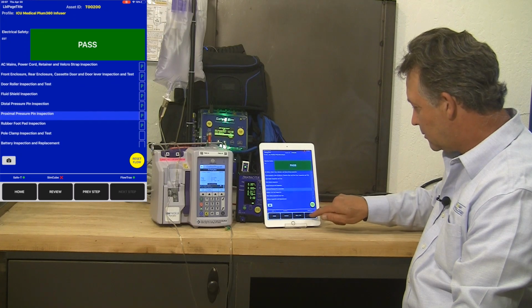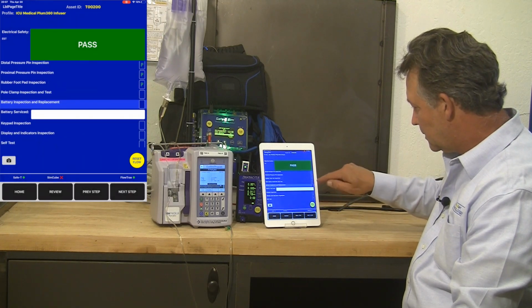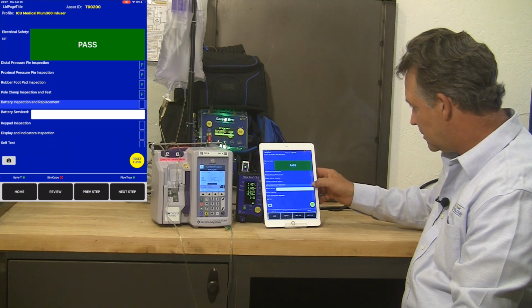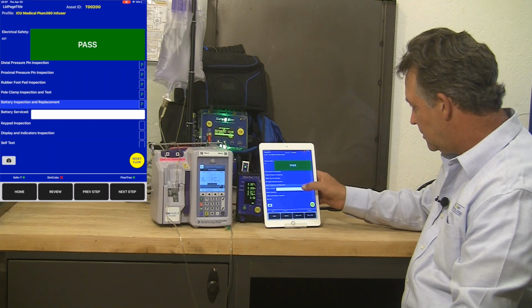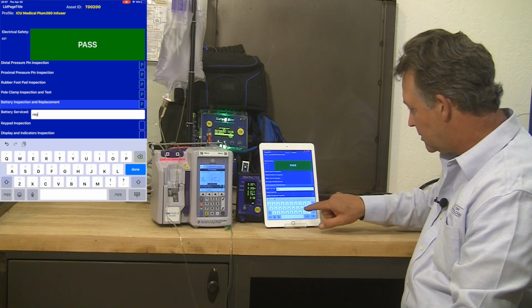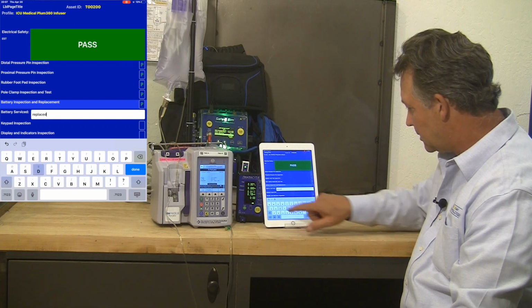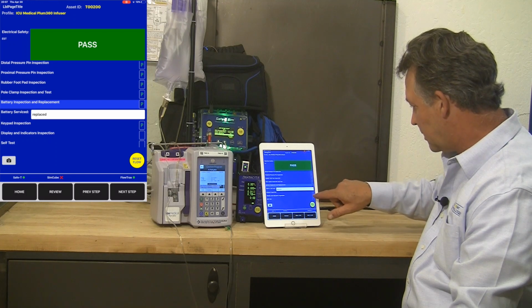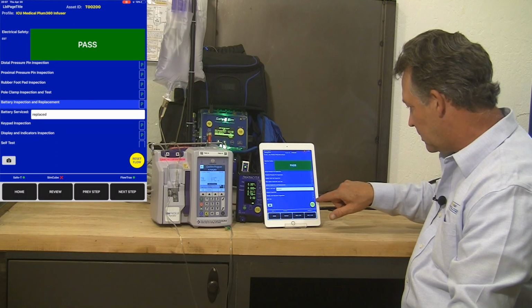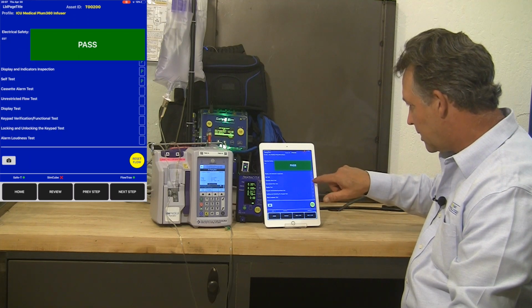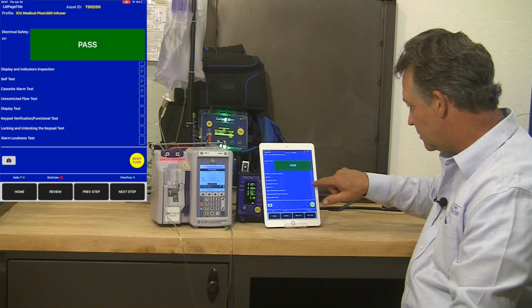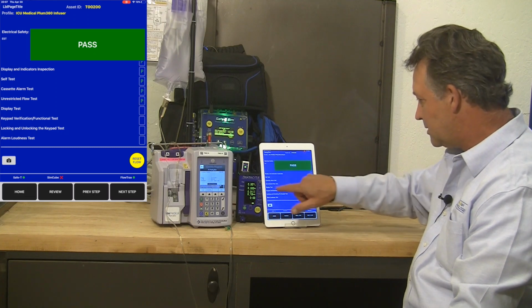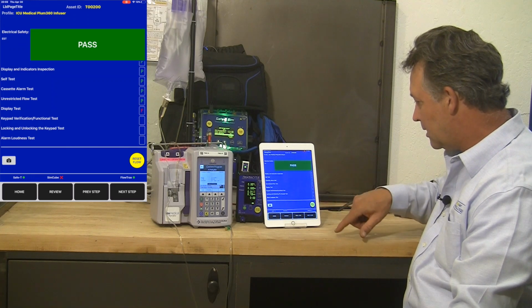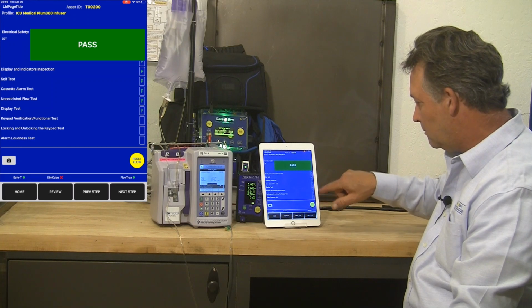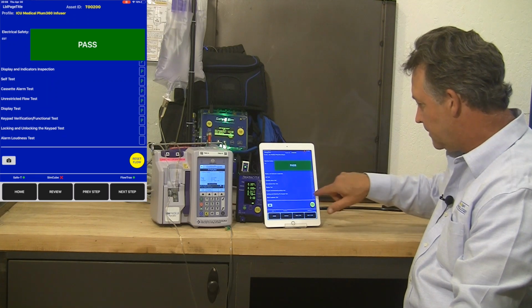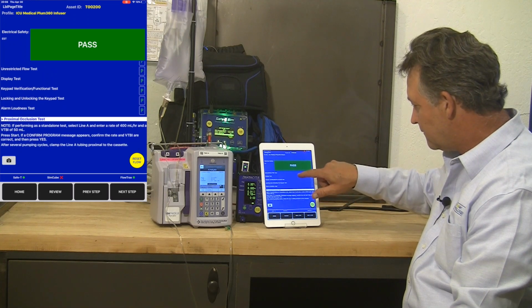I can hit next step, scroll down, and pole clamp inspection and test is where I just touched. Battery inspection and replacement. Battery serviced. I could type in replaced battery, or I could use voice to text to get that in there. Move on to keypad inspection, display and indicators inspection, moving through the checklist and selecting pass-fail depending on the condition. If something doesn't pass, for example, if the display test didn't pass, I could hit the P, tap it again for a fail. We won't do that in this video, but you can select pass or fail for your record. I'm continuing to move through the checklist as I finish tests.